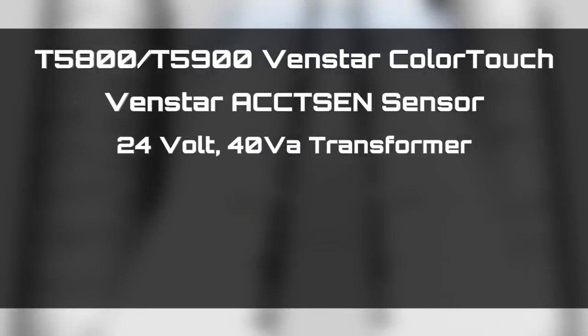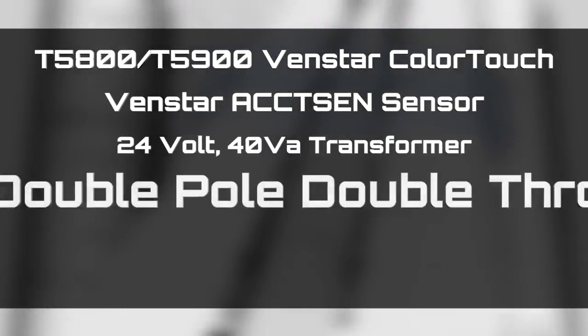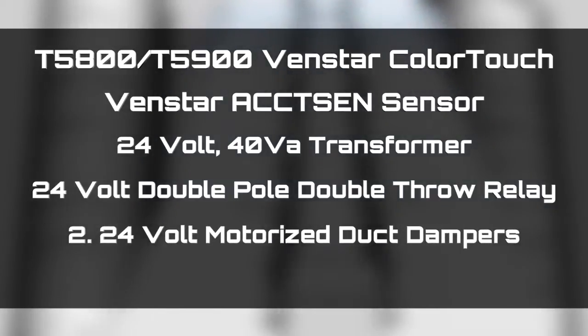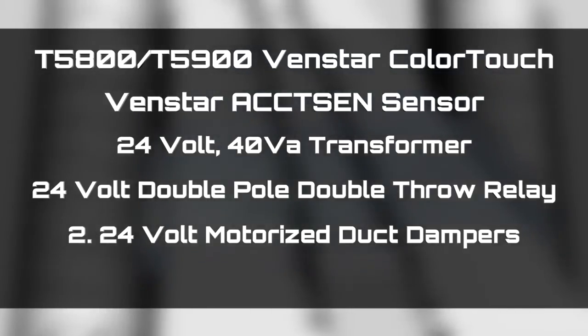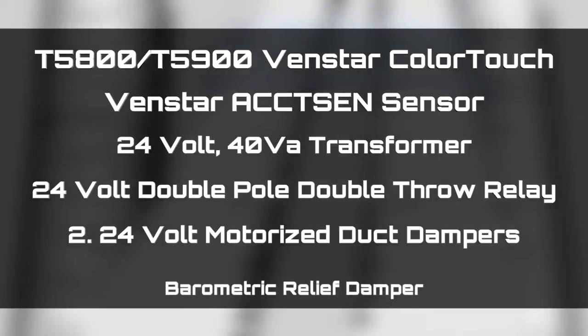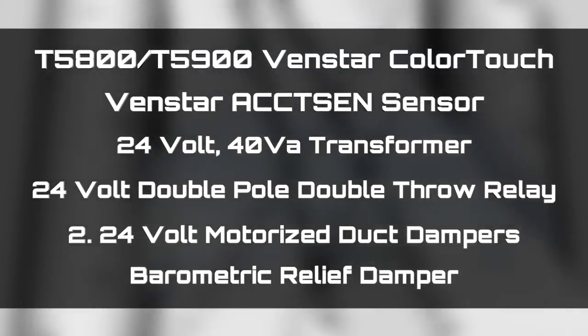Before we begin, let's look at all of the things you will need to make free cooling work. You will need a Venstar Color Touch, a Venstar ACC-TSEN sensor, a 24-volt transformer, a 24-volt double-pole double-throw relay, two 24-volt motorized duct dampers — one for the return air and the other we will convert to a normally closed damper to be used for the air intake from the outside. And finally, a barometric relief damper for relief into the attic.